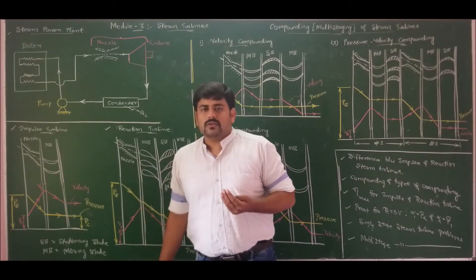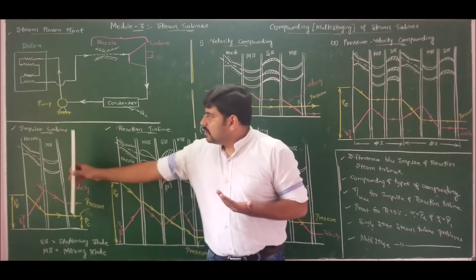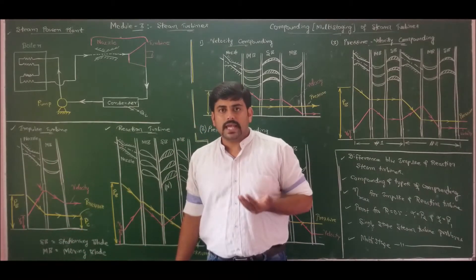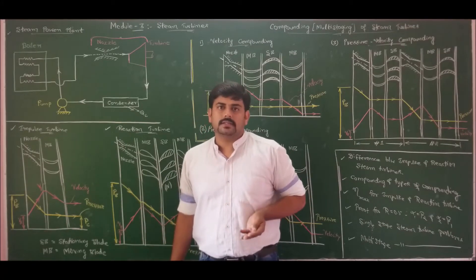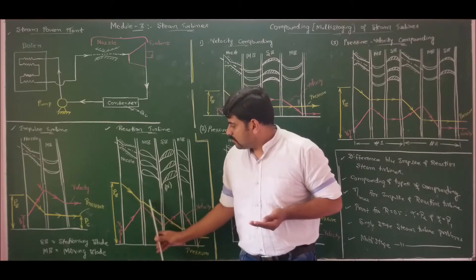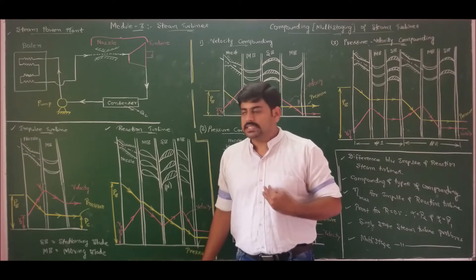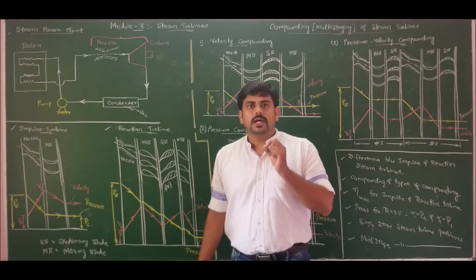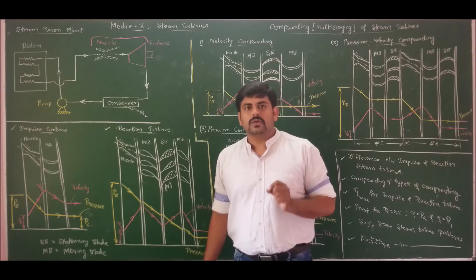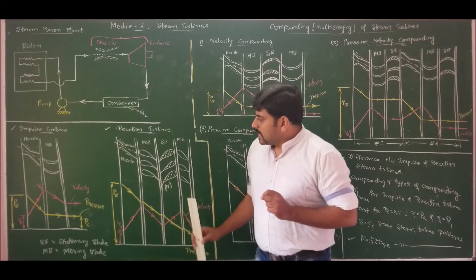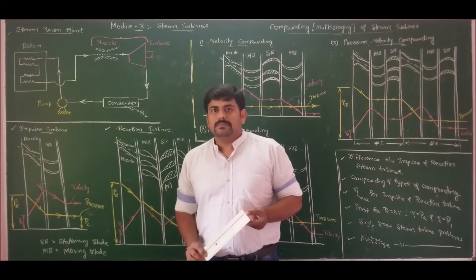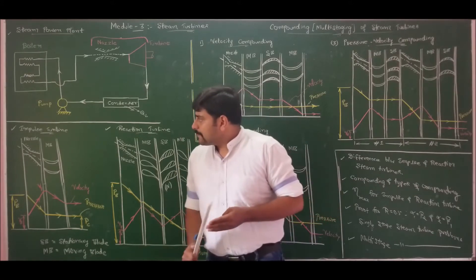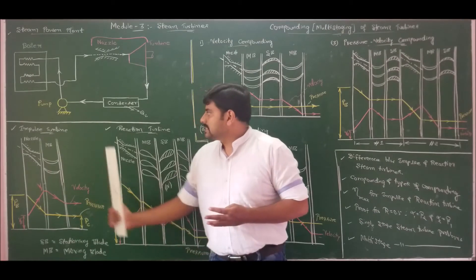Fifth difference — energy supplied: for impulse turbine, energy supplied is given only by the kinetic energy of steam at inlet, that is V1 squared divided by 2gc. Whereas in reaction turbine, since pressure drop is observed both in the nozzle and in the moving blade, energy supplied per kg is V1 squared over 2gc plus (Vr2 squared minus Vr1 squared) over 2gc, which confirms Vr1 is not equal to Vr2 for reaction turbine. Sixth, efficiency of impulse turbine is comparatively less whereas efficiency of reaction turbine is higher. These are the major differences between impulse and reaction turbines.